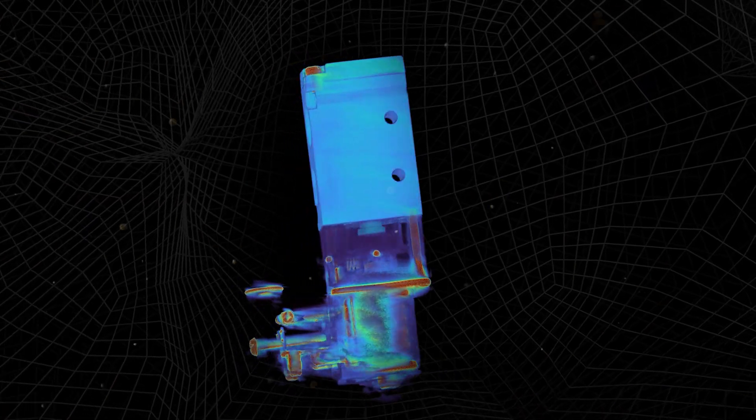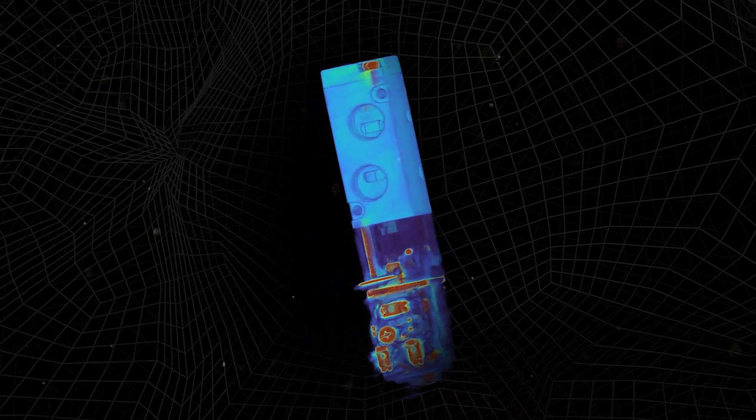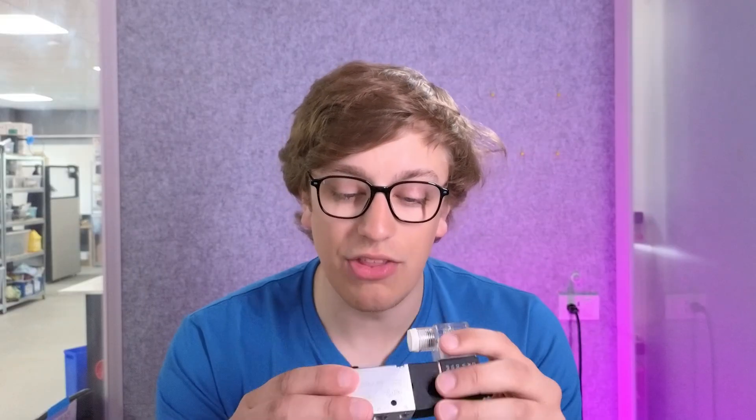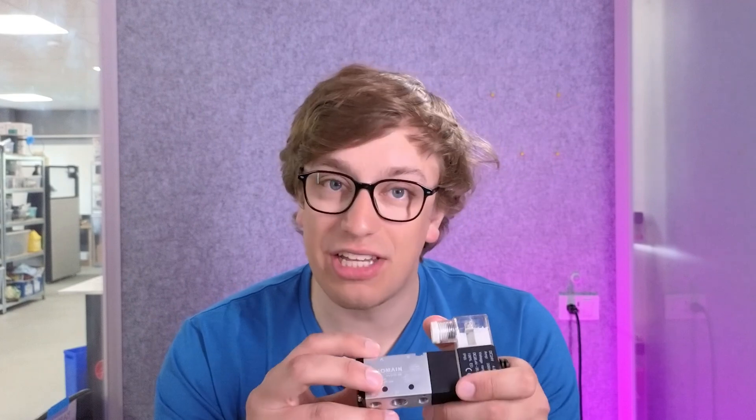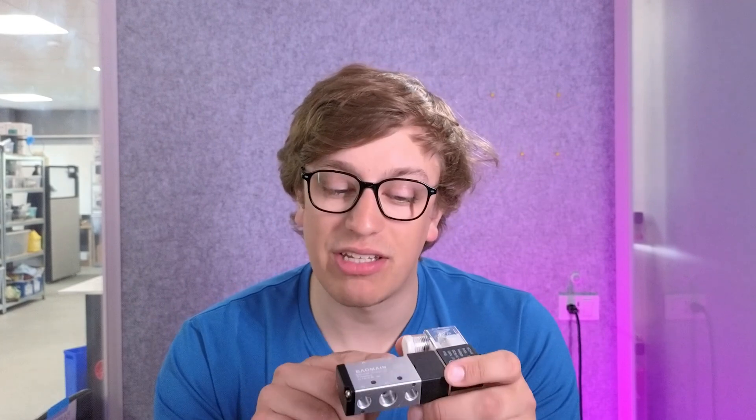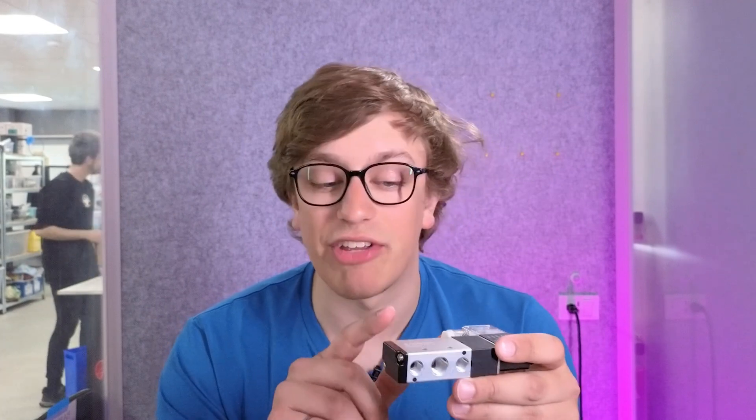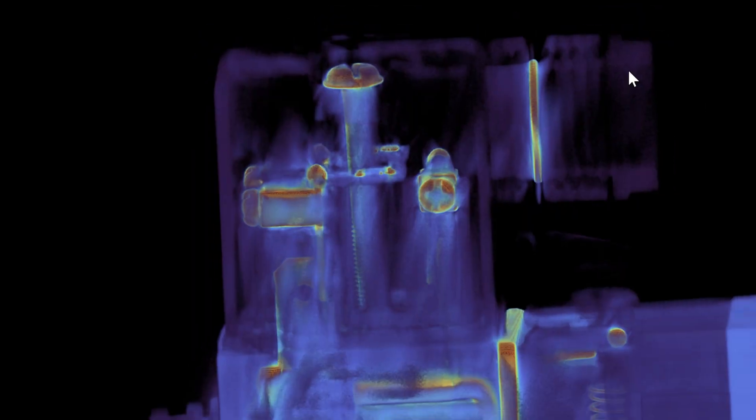So this is a two-position, five-way valve, which means that you can either be directing pressure to the A side and venting the B side, or delivering pressure to the B side and venting the A side.